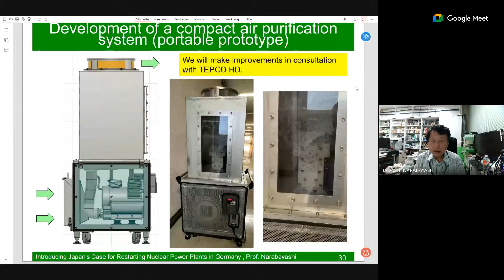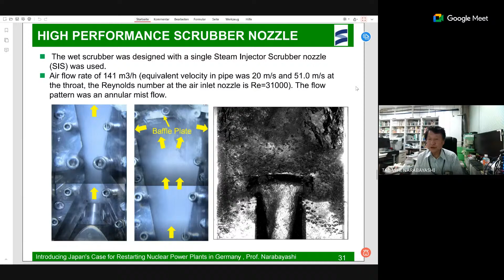And this is the key point, the nozzle of the air cleaning system. A very high performance steam injector nozzle type scrubber was used. The flow rate is 141 cubic meters per hour per nozzle, and about 24 nozzles are used, so it is over 2,000 cubic meters per hour. This is a very high efficiency radioactive material removal scrubbing nozzle. Next, please.